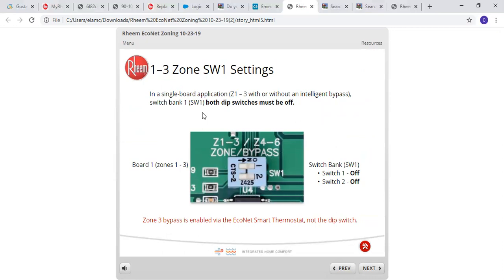Okay, this is your dip switch settings here. In a single board application, with or without intelligent bypass, both dip switches must be off. So if you're doing a single board system, the dip switches are off regardless. Very simple. Even if you're using a bypass, which, if you're doing a 2-zone system or a 2-board system, you have to turn one of them on for the bypass. But on a single board system, both dip switches will be off. Zone 3 bypass is enabled via the Econet smart thermostat and not the dip switch.